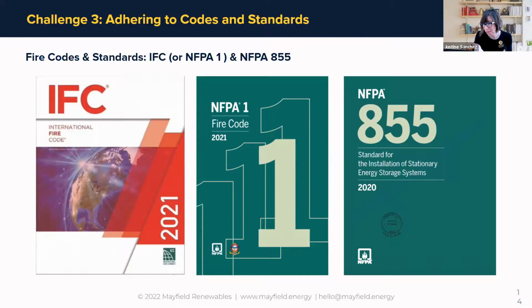I'm a pretty big fan of this effort to make our installations safe. The other document we have up here is NFPA 855, which was put out in 2020, and that really informs the 2021 versions of the IFC, IRC, and NFPA 1. California and New York are really the leaders when it comes to requiring these most current up-to-date rules with energy storage. This book, NFPA 855, came after we had that big accident in Arizona with the 2 megawatt plant, sending 9 first responders to the hospital, 3 of them with serious, longer lasting injuries. It was a big deal, and there's a lot of attention on energy storage and how to install it safely.